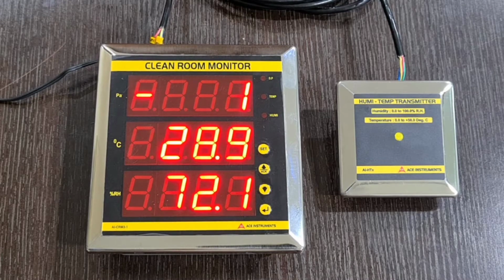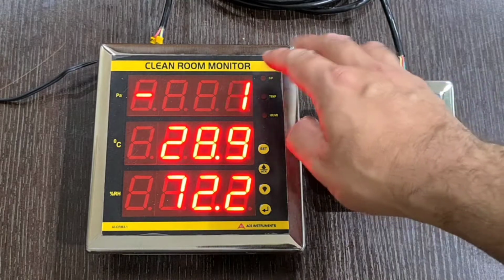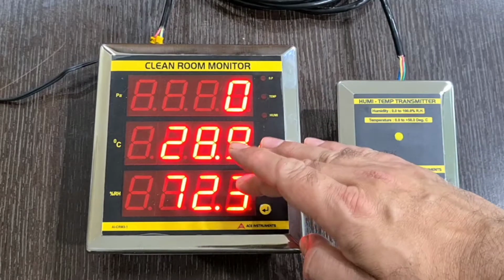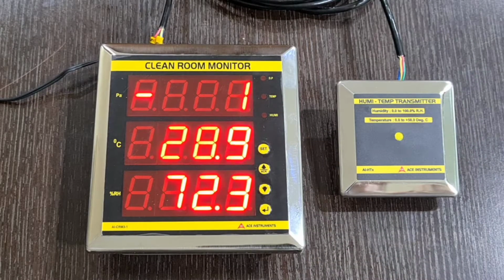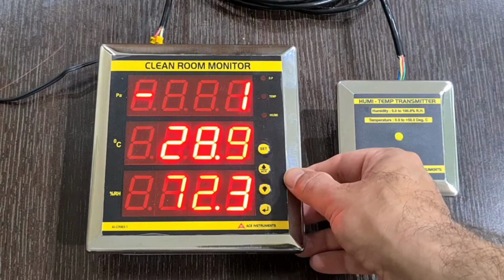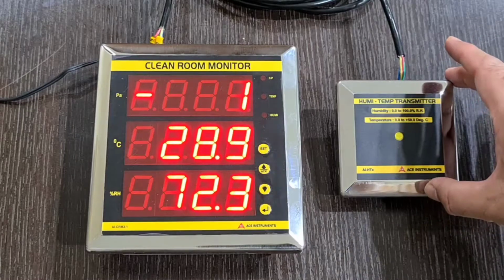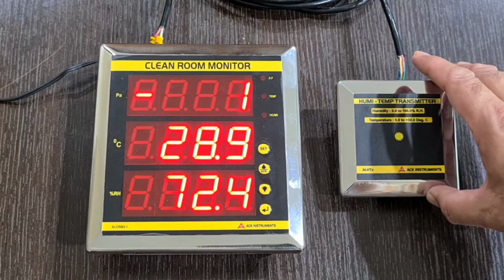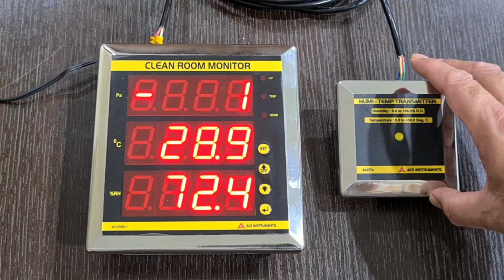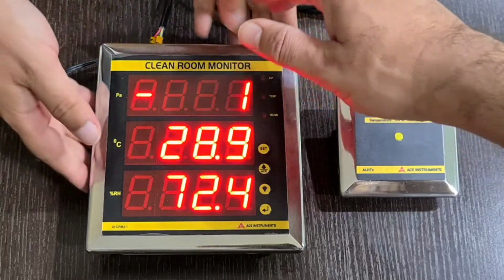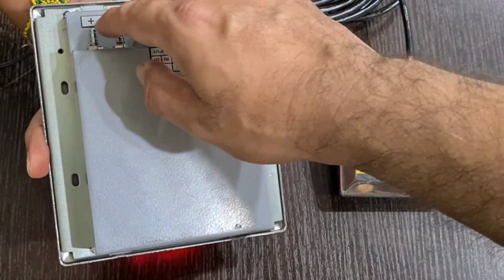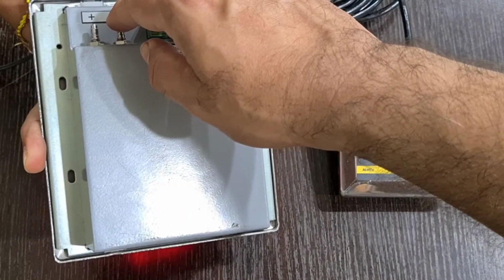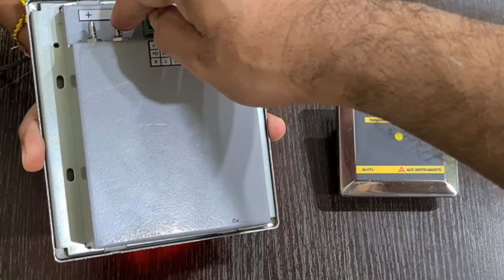I'll guide you through a detailed video here of the ACE Instruments Hospital Cleanroom Monitor, the model AI-CRM 3.1, which monitors the critical parameters of differential pressure, temperature, and humidity in hospital operation theatres and clean rooms. This is a flush mounting type instrument with an external combination temperature humidity sensor, again in a stainless steel flush mounting plate, and also a differential pressure sensor which is built inside the instrument and has the two hose nipple connections, one for positive and one for the negative pressure at the back.